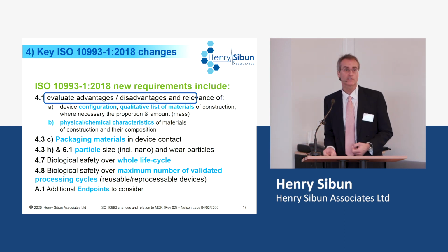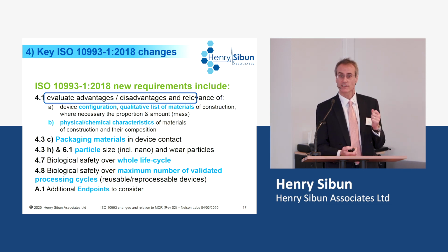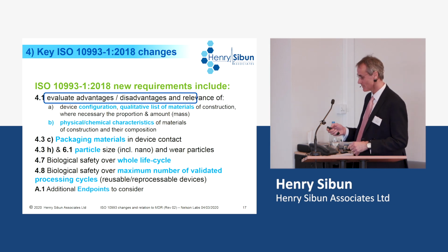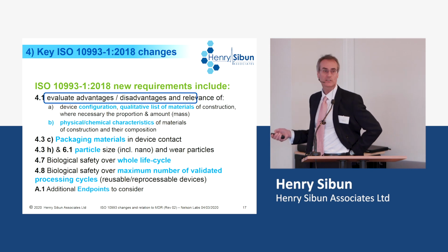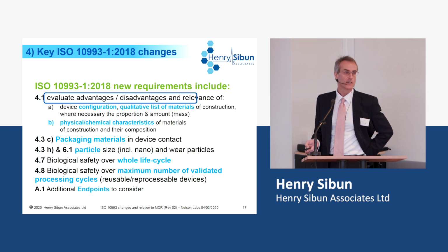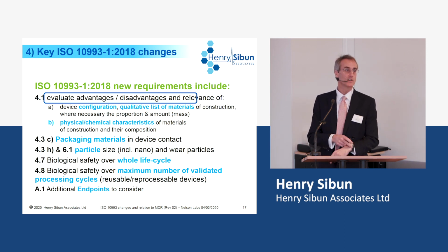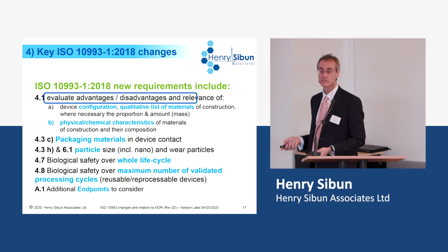I know from my experience, if you took 5-year-old PVC tubing and you squeezed it, it felt physically harder than tubing that was new, even though it's the same tubing. It's a very subjective test. I'm not suggesting you should use that, but you can notice the change over time. And if you have devices which are reprocessable or reusable, you need to consider the maximum number of processing cycles. So if the device can be used 200 times, you need to reprocess 200 times and then consider your extractables, leachables, chemical nature, and everything else. And that's quite a big bunch of work.